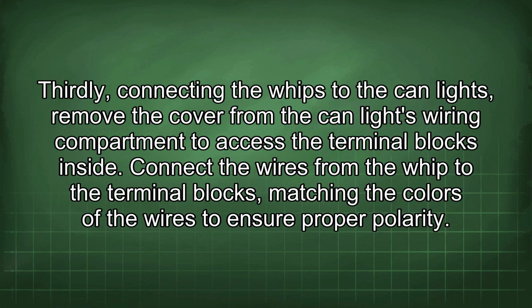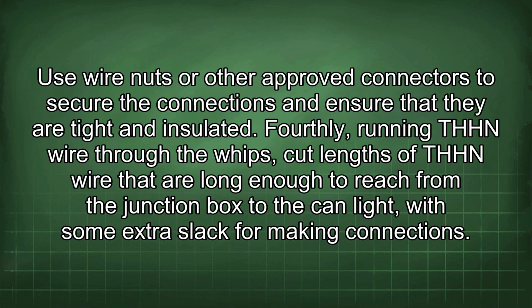Thirdly, connecting the whips to the can lights. Remove the cover from the can light's wiring compartment to access the terminal blocks inside. Connect the wires from the whip to the terminal blocks, matching the colors of the wires to ensure proper polarity. Use wire nuts or other approved connectors to secure the connections and ensure that they are tight and insulated.